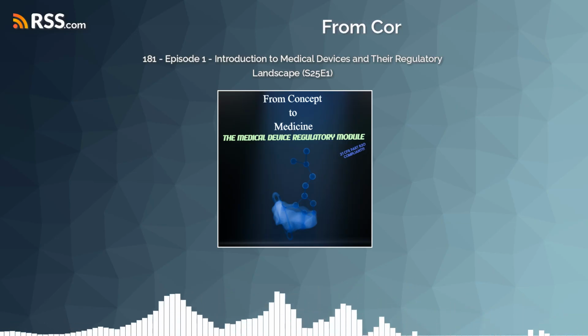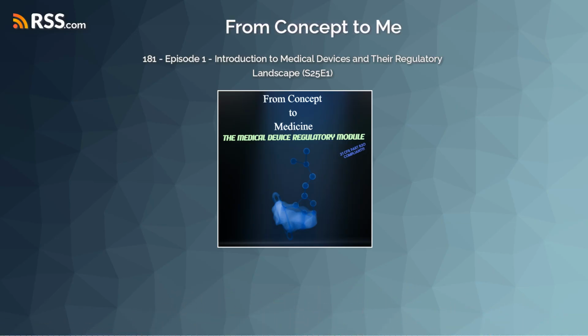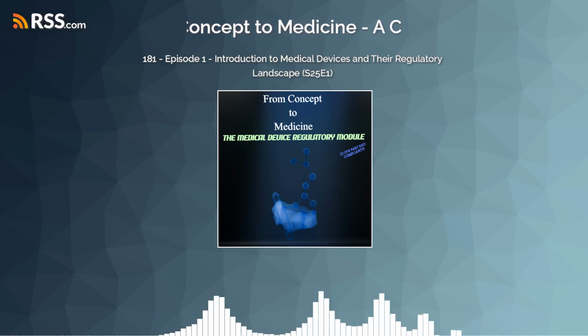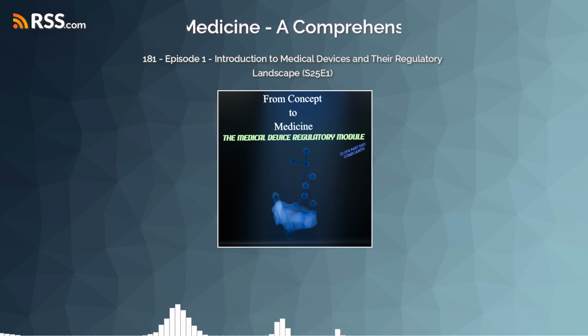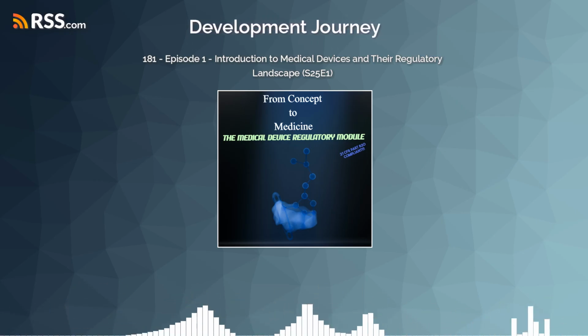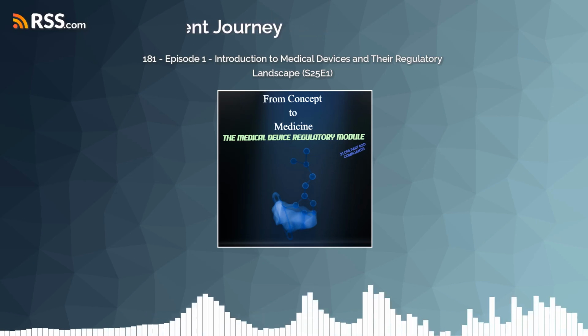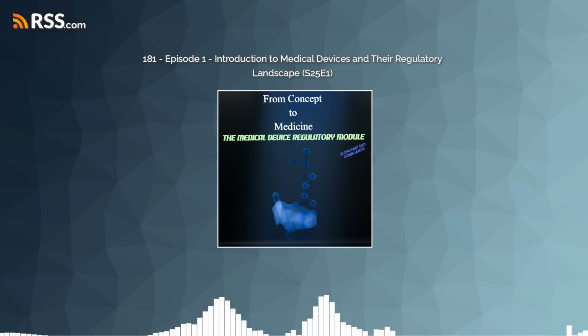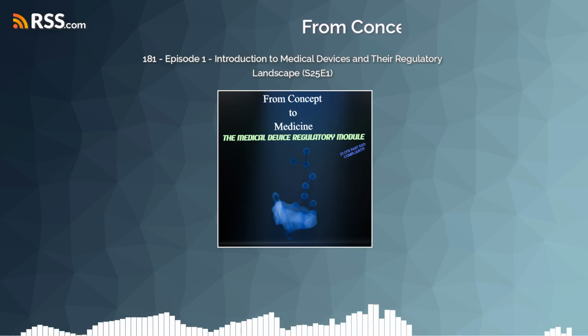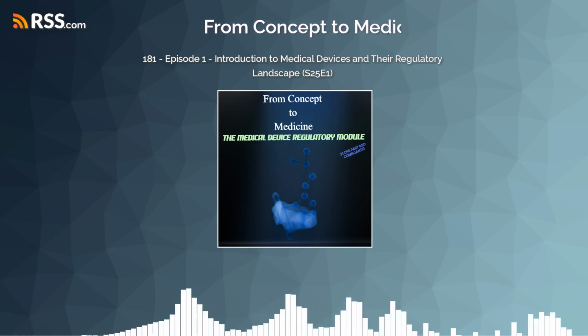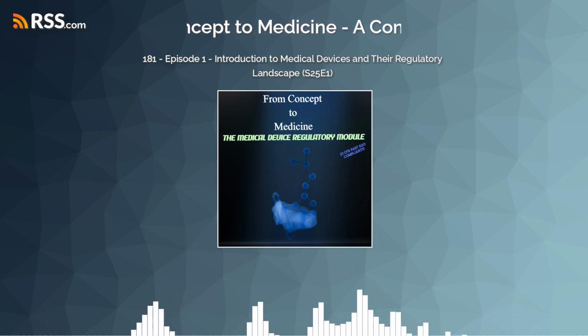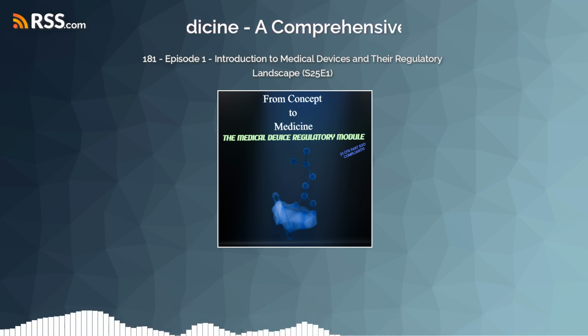That's exactly where the de novo classification pathway comes in. It's specifically designed for novel, first-of-a-kind devices that are generally low to moderate risk, but have no existing predicate device. So a manufacturer submits a de novo request. If granted, the FDA creates a new classification for that device type, classifying it as either Class 1 or Class 2, and establishes any necessary special controls right then and there. So it sets the standard.